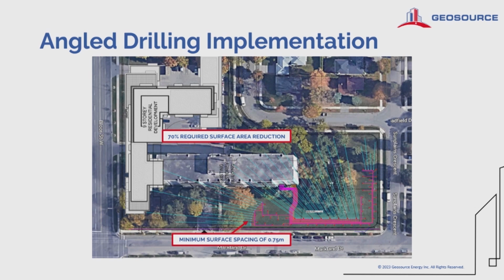In this image, you can see a satellite image of the site overlain with our CAD plan view of the bore field. The red dots indicate vertical boreholes going into the page. The teal lines represent the trajectory of angled boreholes projected up onto the horizontal surface. And I guess you can't see it here, but orange and pink lines represent horizontal runout piping that connects the bore field to the geothermal mechanical station.